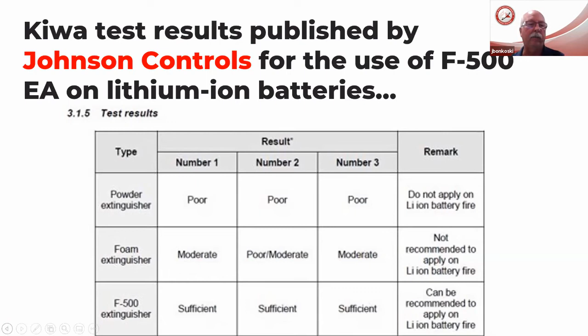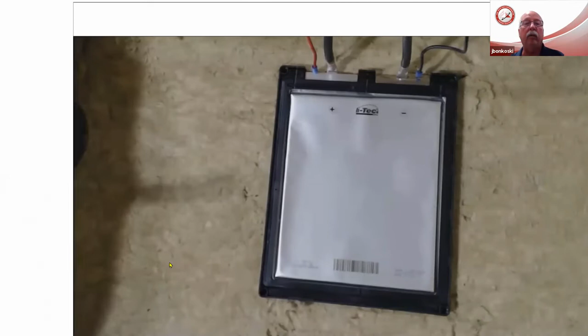Let's look at F500 encapsulator agent. They give that a sufficient all the way across the board, and they do make the recommendation to apply on lithium-ion battery fires, because in their testing they were able to show that they could stop thermal runaway in lithium-ion batteries. And right now, as you can see in the conclusion for Johnson Controls, it's able to stop the lithium-ion. It has a direct impact on being able to cool, unlike foams, and it's able to suppress those vapors and encapsulate the electrolytes that would be part of an ongoing hazard.